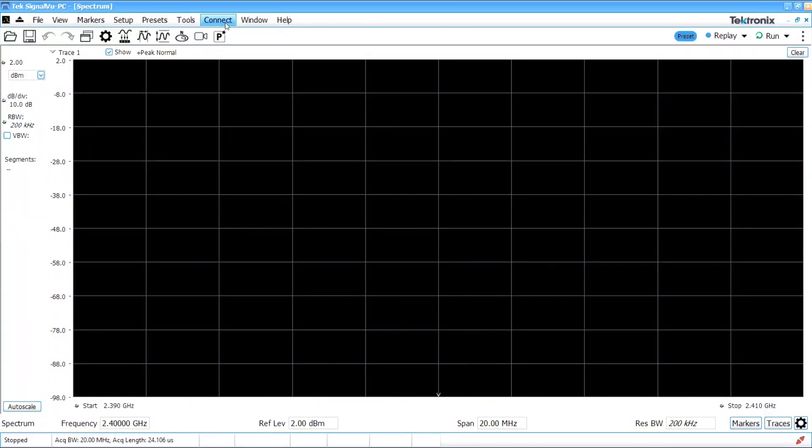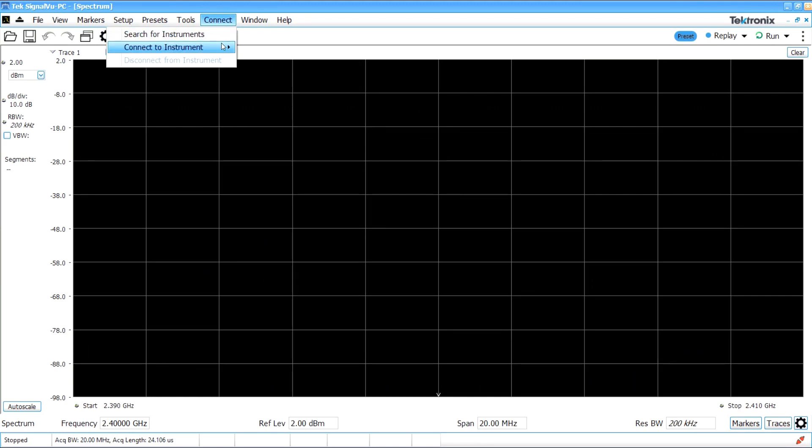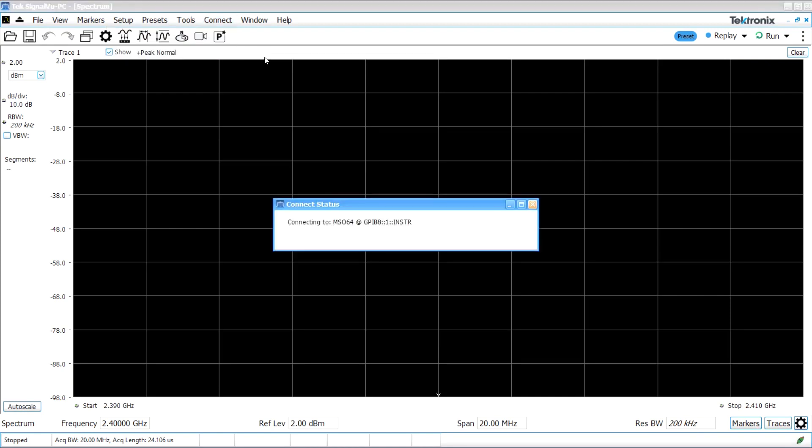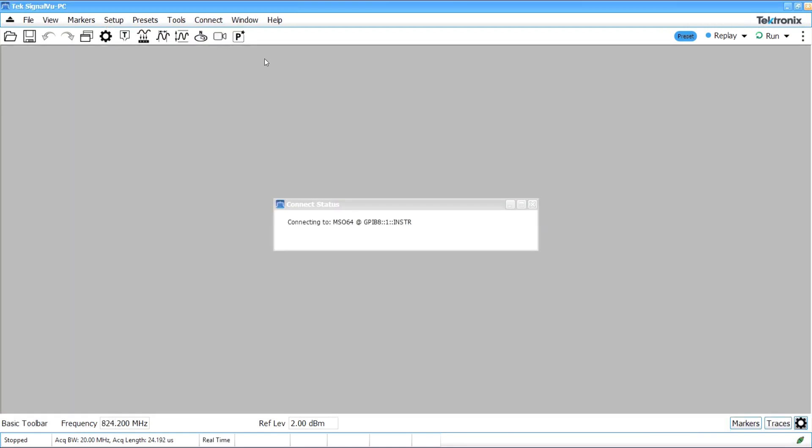Once SignalVu-PC finishes launching, click on the Connect menu and scroll down to Connect to Instrument. You should see the oscilloscope on the list. Once you click on it, it will establish the connection to the oscilloscope.